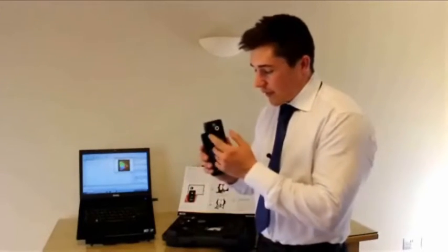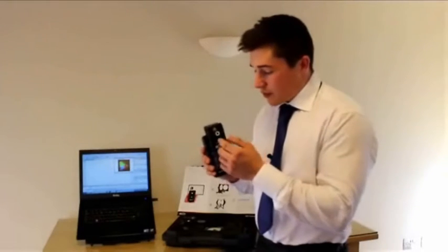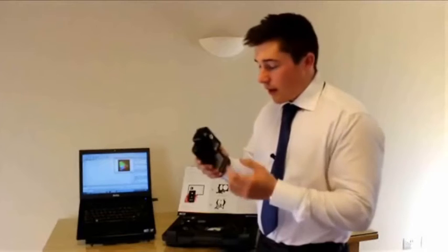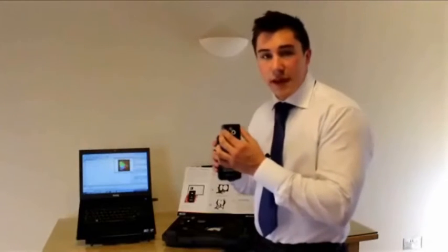Inside the sphere here, we have a coating called barium sulphate. This means that once your LED unit is placed inside, the light is reflected to about 97%. So you have a good diffused reflectance inside the sphere.